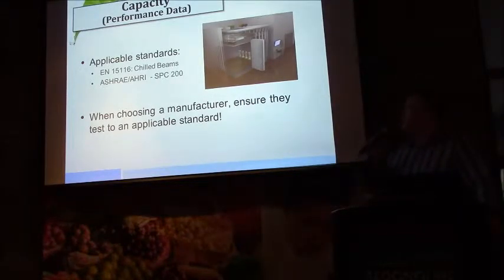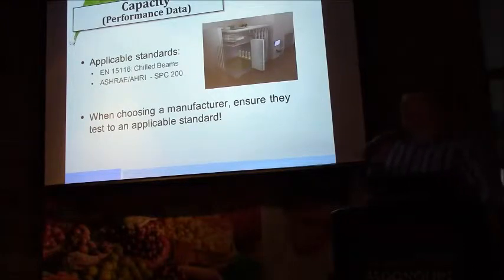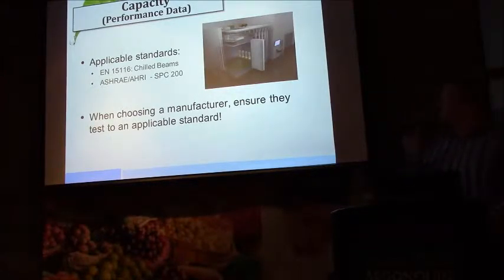This discussion effectively centers around proven performance or tested performance. The European standard is EN15116. This is the calorimeter chamber that measures the thermal capacity of the beams. The more recent standard, which was developed through ASHRAE and AHRI, is through the Special Project Committee, SPC 200, which is out for public review and may be issued shortly, if it's not out already, actually. But when manufacturers, again, beams are sheet metal boxes with coils in them, ensure that this standard is adhered to, you can be confident that the capacity can be achieved through each of those pieces of equipment.